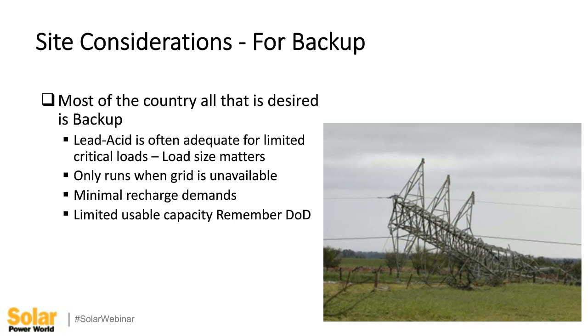For backup, it only runs when the grid is unavailable. There are minimum recharge demands—if your power only goes down 3 times a year, you're only going to be recharging it those 3 times, maybe a few times each. And then there's limited usable capacity with lead acid, so if you select this, make sure you understand that the depth of discharge is going to be limited and size it accordingly.